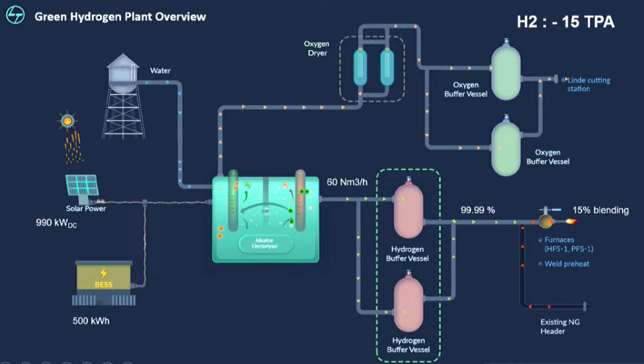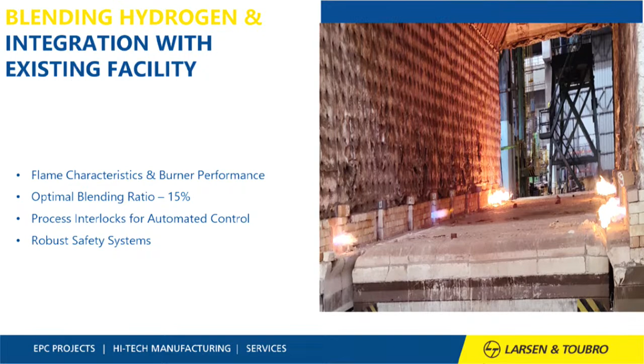This is just the statistics of this. Another very critical part is where hydrogen is being used. We did extensive collaborative testing with our burner suppliers for these furnaces to understand the limit of hydrogen that can be blended with natural gas in as-is condition. After that analysis, we arrived at a 15% blending rate. Our piping was analyzed so there's no adverse impact of hydrogen blending. After this, with safety precautions like gas detectors at the point of application, we implemented and commissioned it successfully.